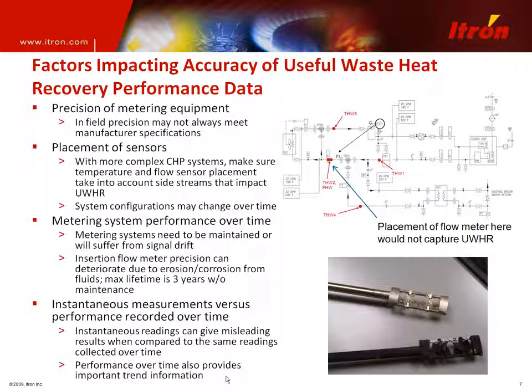Okay, so what might be some of the factors impacting the accuracy of useful waste heat recovery performance data? As Bowen mentioned early on, you have precision of the metering equipment, and in fact, the in-field precision may not always be what is specified by the manufacturer, just simply because there can be different circumstances than what you'll see under the equipment spec. Placement of sensors is critical. Again, we're talking about useful waste heat recovery and not just the waste heat offset by the generator. So you have to really make sure that you're placing your temperature and flow sensors appropriately, and you take into account any sort of side streams that might impact what you're considering to be useful waste heat recovery.